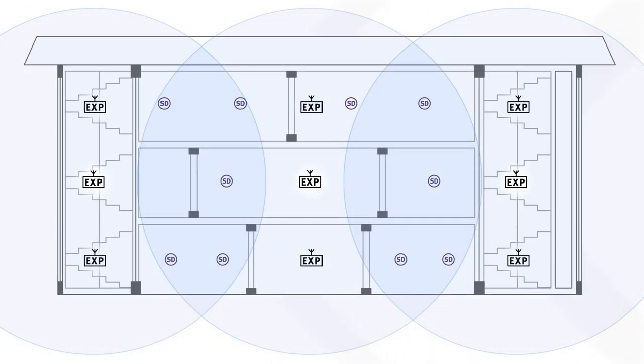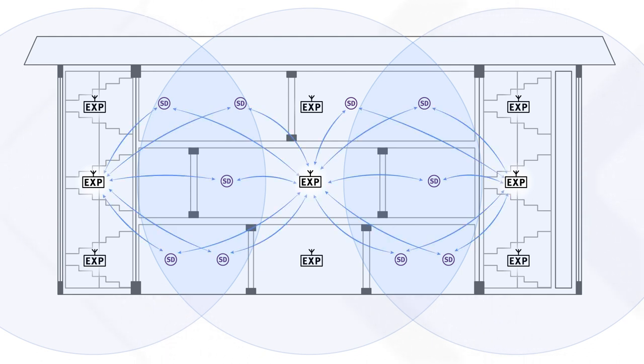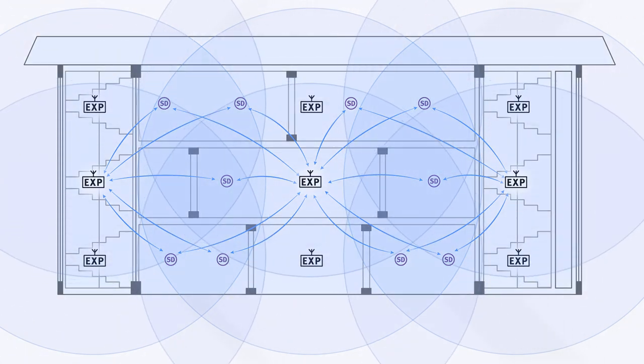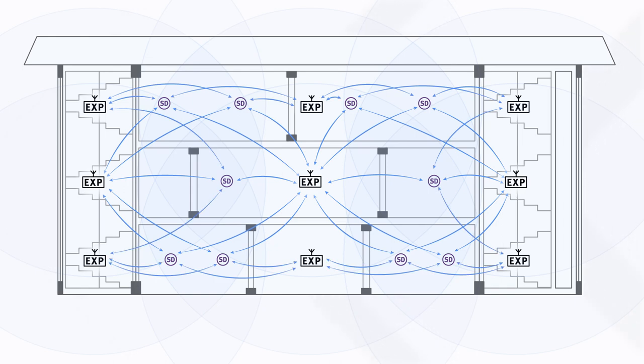It's also important to note that the antenna pattern of an expander is spherical, which means that it can connect to devices one floor below or above it. Since there is a lot of overlap in communication areas of the expanders, most devices in the building have multiple backup connections to the network.